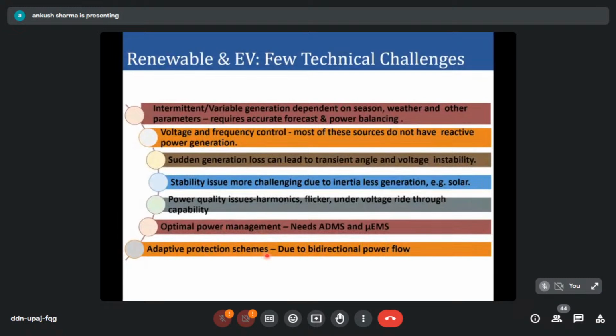Then adaptive protection schemes, because we now have bidirectional power flow. That means the conventional protection schemes are no longer working. You need an adaptive protection scheme which can address the bidirectional power flow, because right now the system is designed for unidirectional power flow. Once the power flow reversal happens, the system will consider it a fault and the relay will operate. But when we have more renewable energy penetration, bidirectional power flow will be a common phenomenon, and we need to change our protection settings.